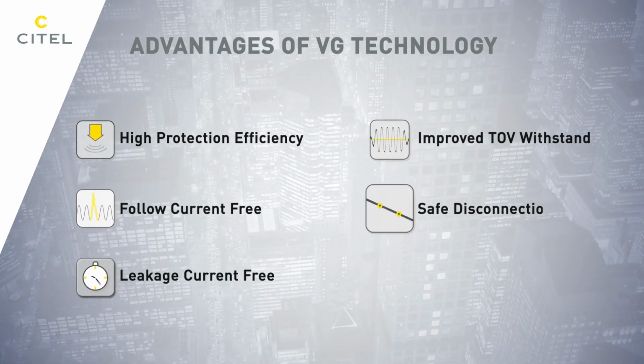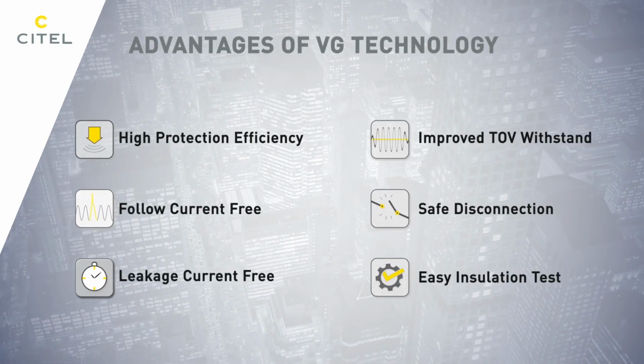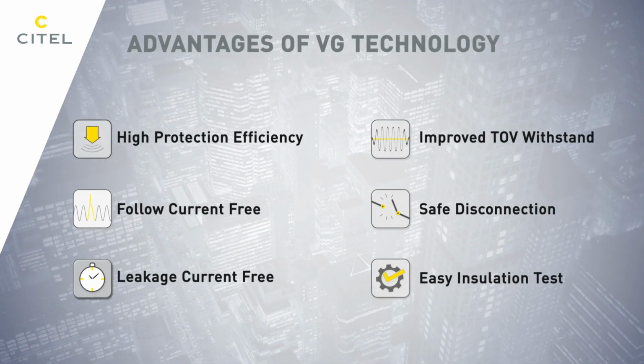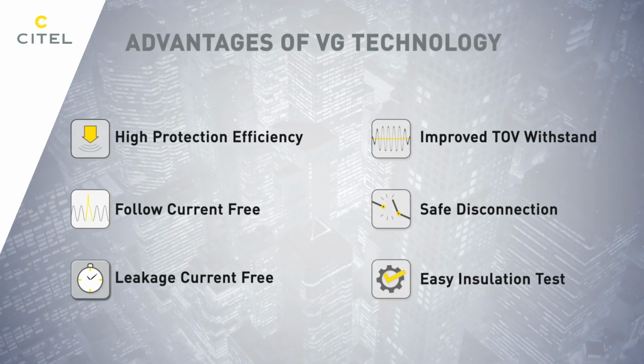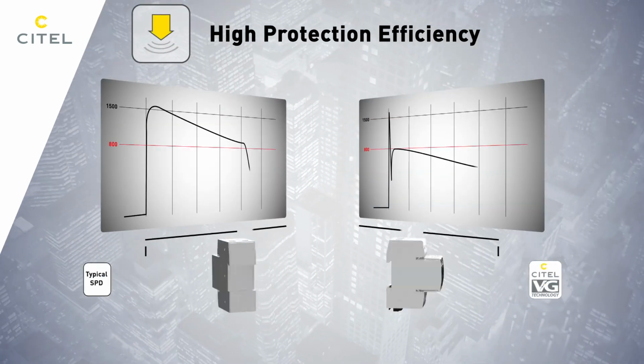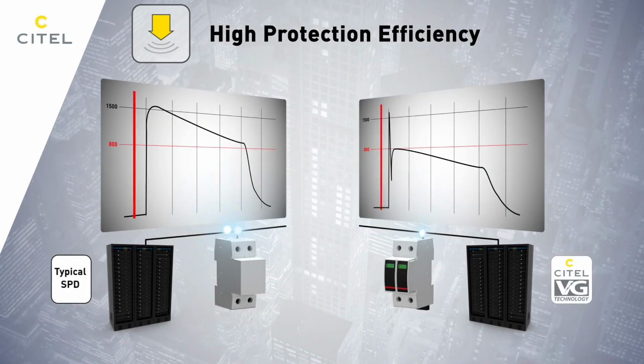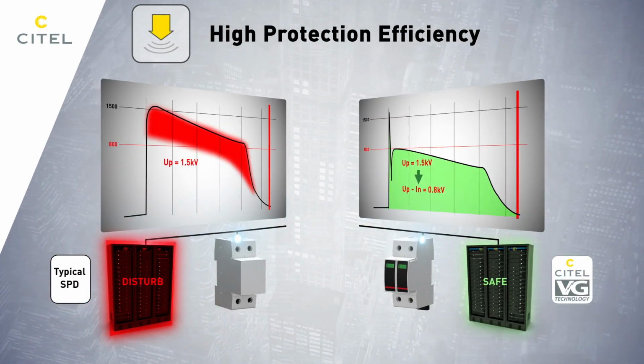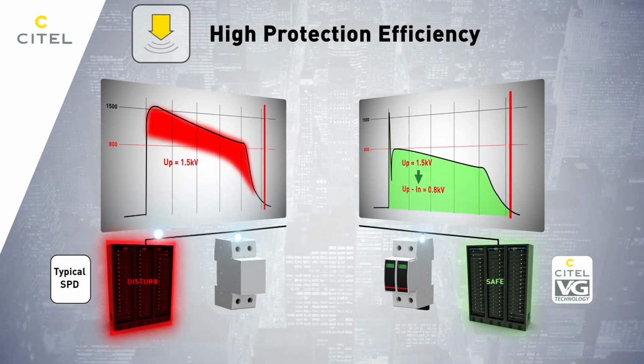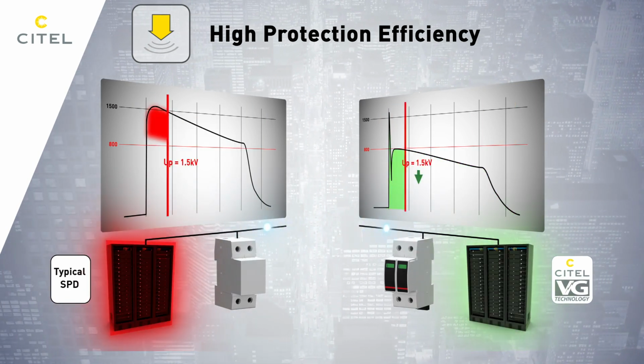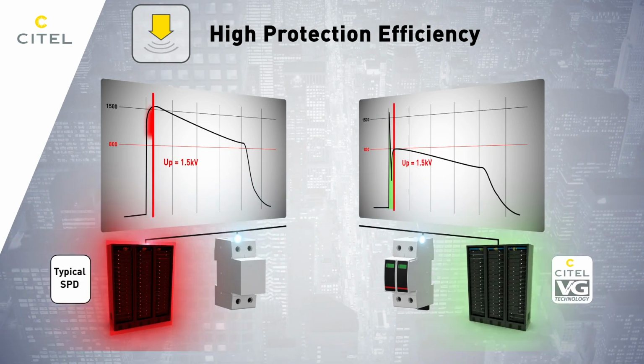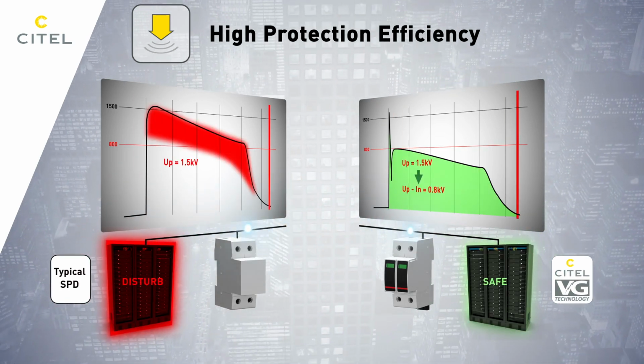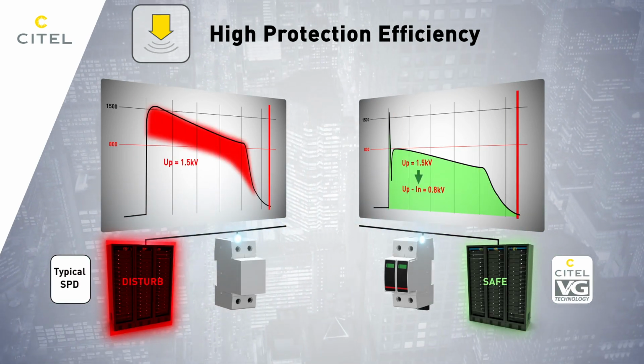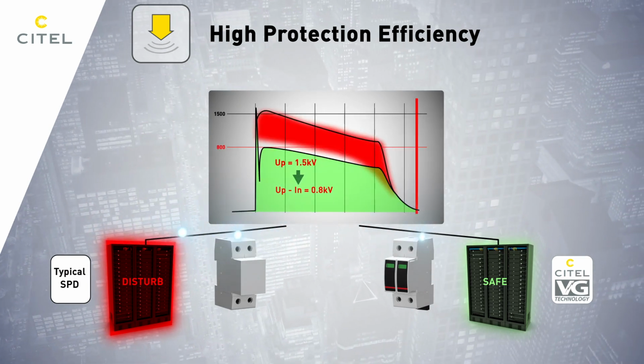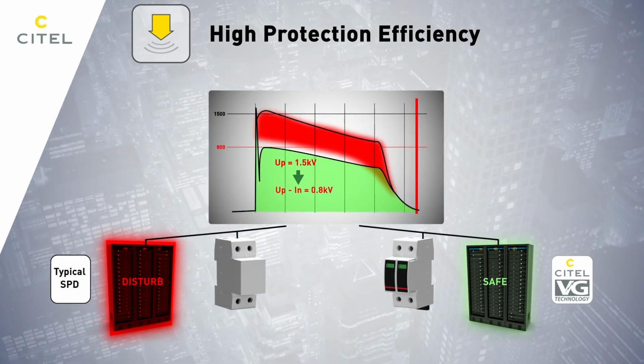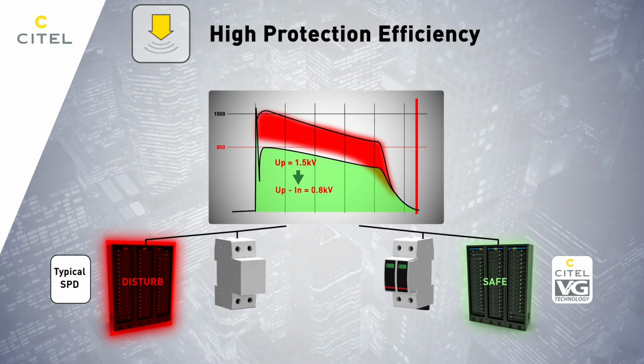There are many advantages to using VG technology when applications require reliable operation and effective protection. The first advantage of VG technology is the high protection efficiency. When a surge occurs, part of that energy inevitably passes through the surge protection device and reaches the protected equipment. This is called let-through energy. If too high, it can damage sensitive equipment. With VG technology, this residual energy is drastically reduced.